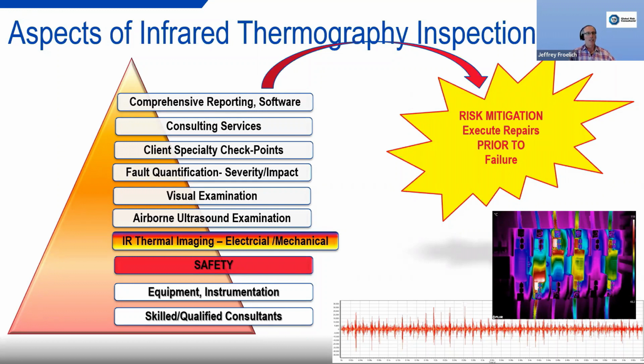We have the visual examination piece, and that's going to do all the non-thermal elements, you know, deteriorated bad wiring practices, contaminants, code busting type items, whole slew of other things. We're going to quantify our faults with severity and impact ratings, and you want to use good internationally recognized categories and standards for that. We have a 4-star scale. You're going to go from a 1, which is a minor, 2 to an intermediate, 3 to a serious, and 4 to a critical. And there are temperature thresholds, delta temperature thresholds for each of those categories. And then you're going to assign a combination impact rating to it, high, moderate, and low. And you're going to tag a loss estimate to it. You're going to tag an equipment criticality to it.